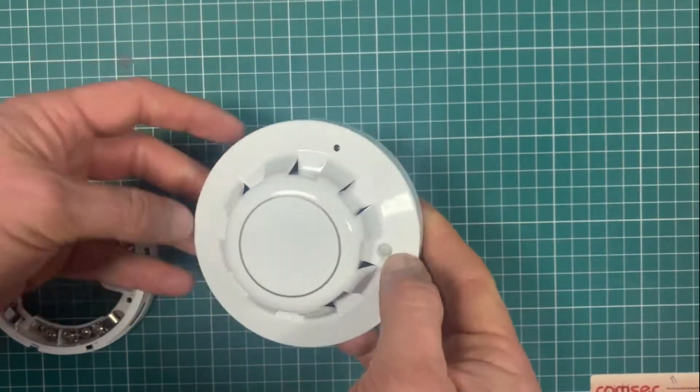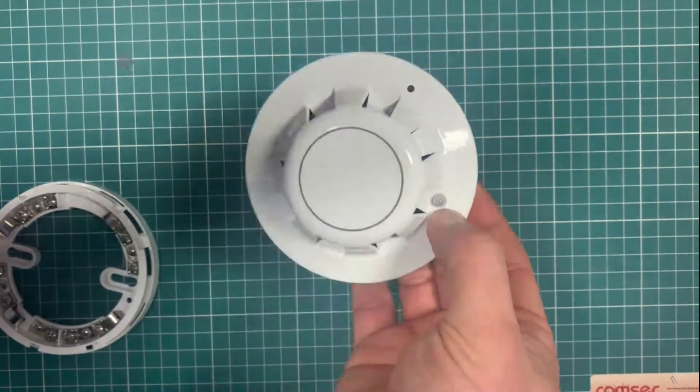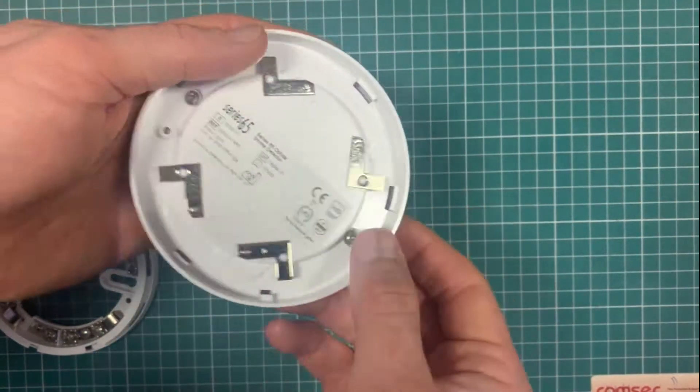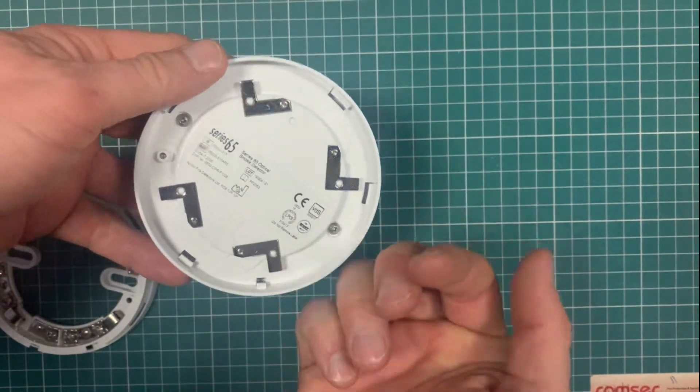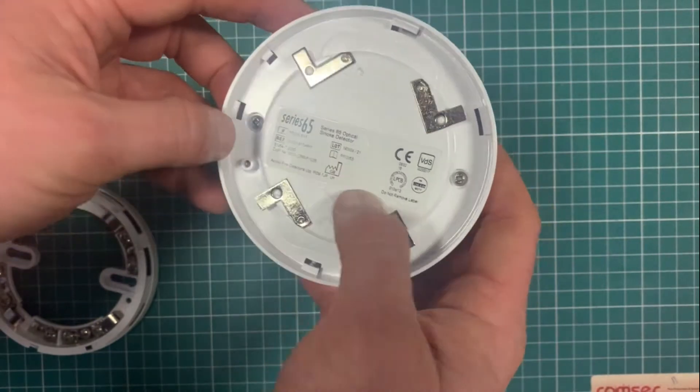The optical detector, little known fact, has a clear LED. If you're looking at the ionization one, it has a red LED. So if you're ever looking at it from the floor level below and wondering whether it's an optical or an ion, that's a way of telling.